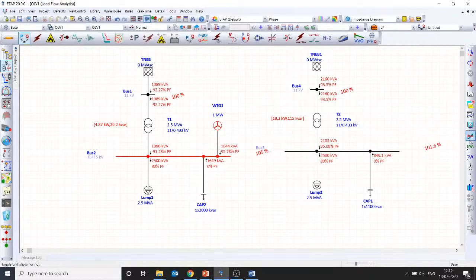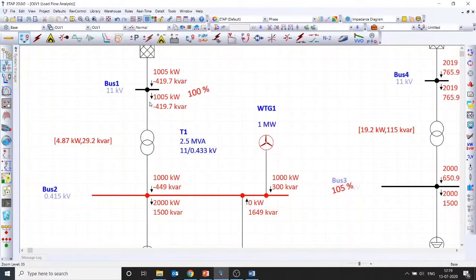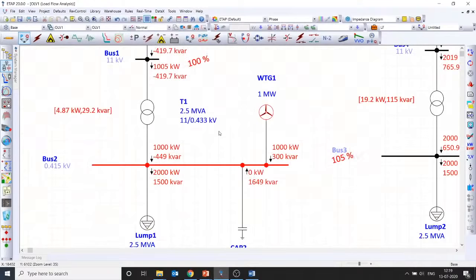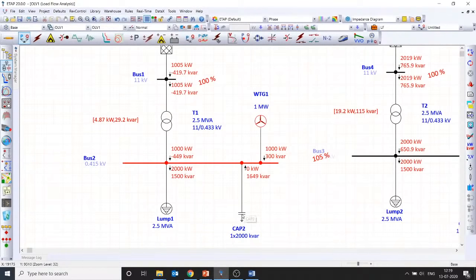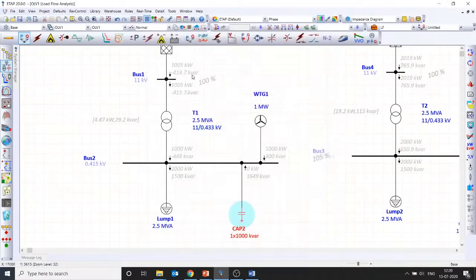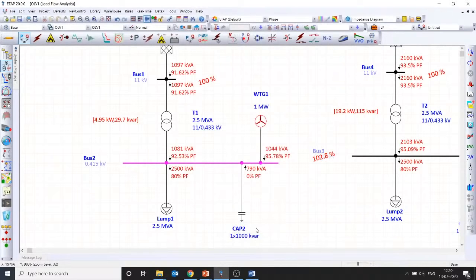If I again plot kilowatt and kVAr, you can understand one more thing. Yes, reactive power is in the reverse direction. Let me zoom in a bit more. Yes, reactive power is in the reverse direction. That means when you use a doubly fed induction generator, you have the option to reduce the capacitor bank ratings. Even with maybe a 1000 kVAr capacitor bank itself, you will be able to maintain a much better power factor. Yes. Perfect. You can see, even with a lower capacitor bank rating, we are able to maintain the better power factor.